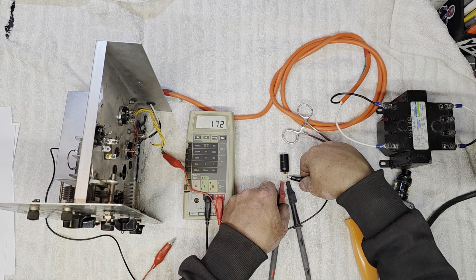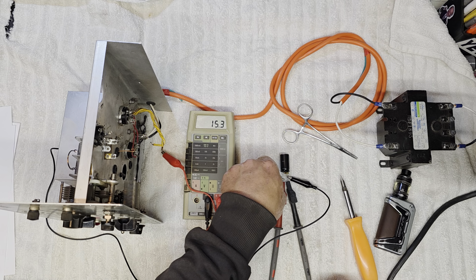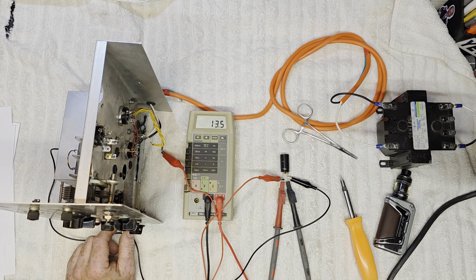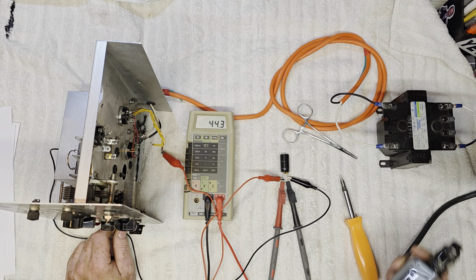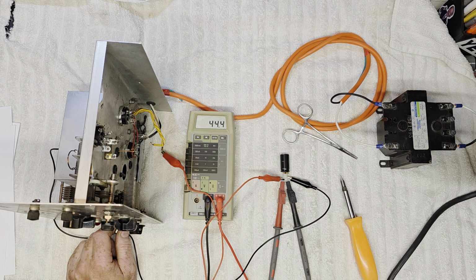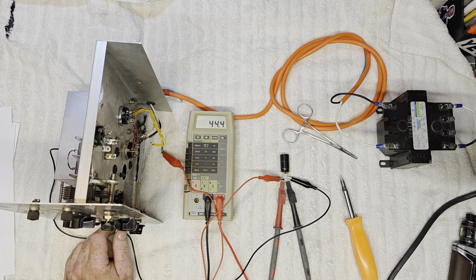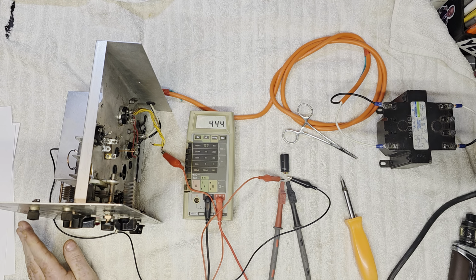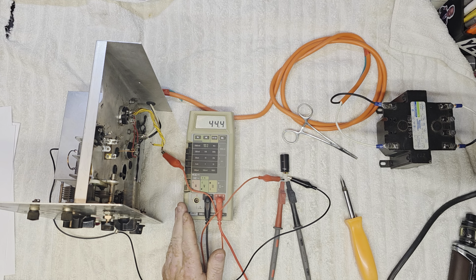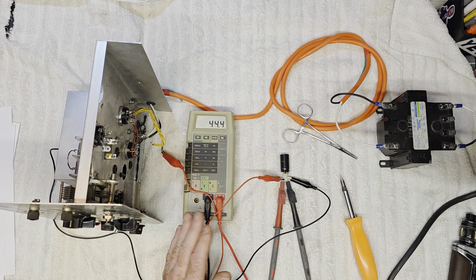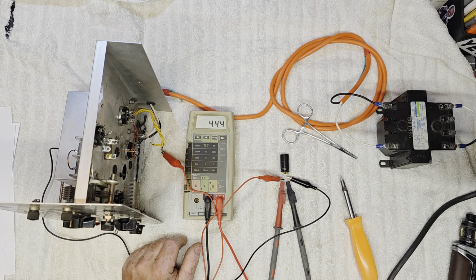Now this should read half that voltage when we turn it back on. We were almost at 90 before. Now we turn it on: 45, 44.3, that's almost 45, that's half of 90. Remember, all these numbers are a tenth. So if you come off the bridge rectifier and off this center tap, that would be 440 volts. We're only at 44 volts right now because we're only running a tenth of the stuff.